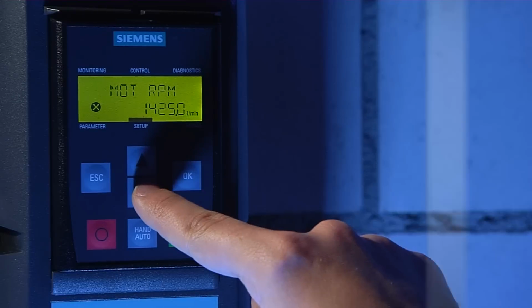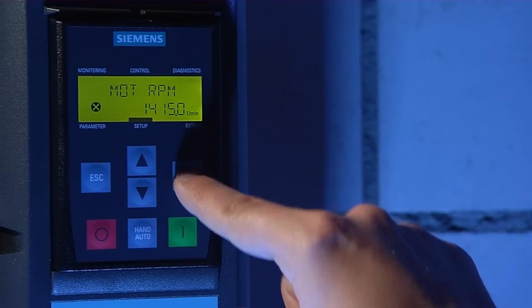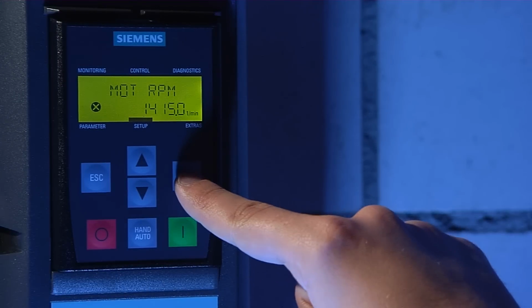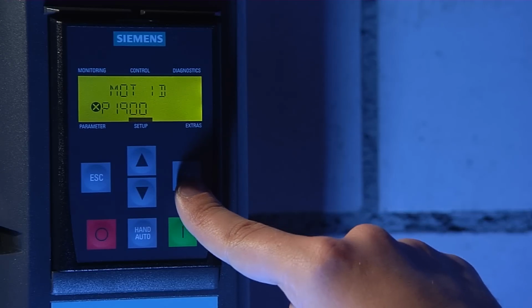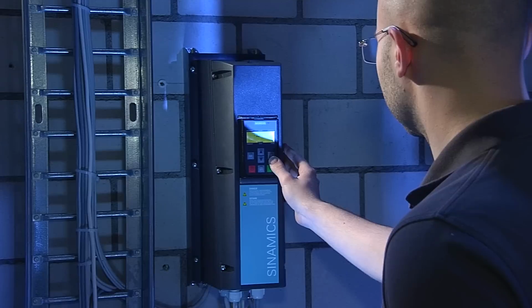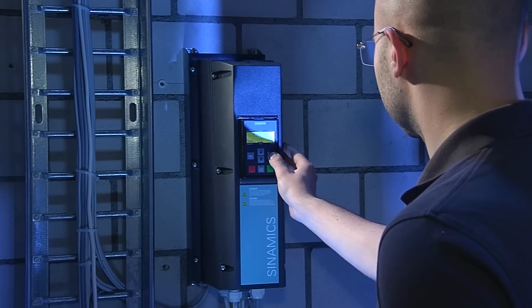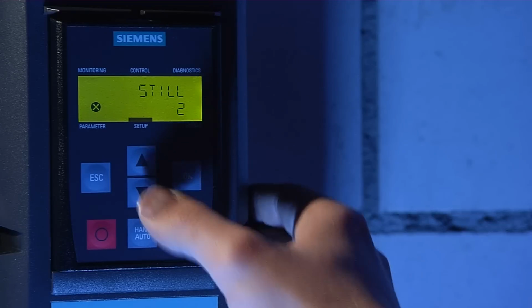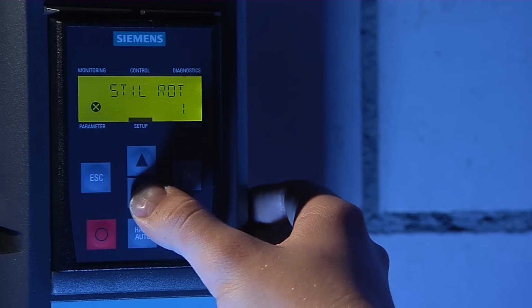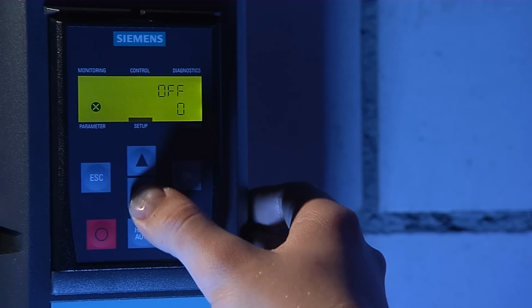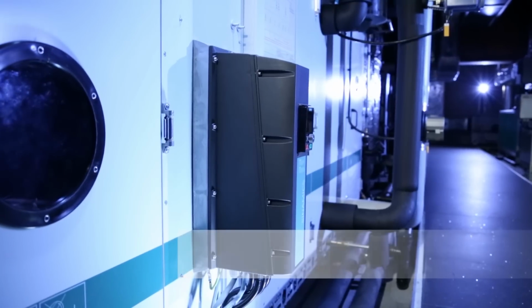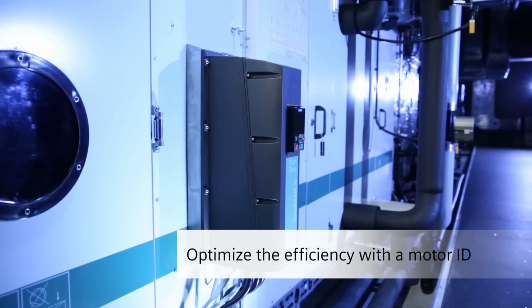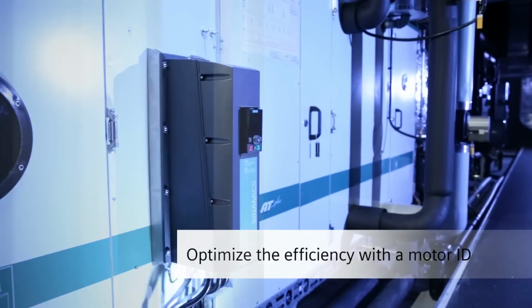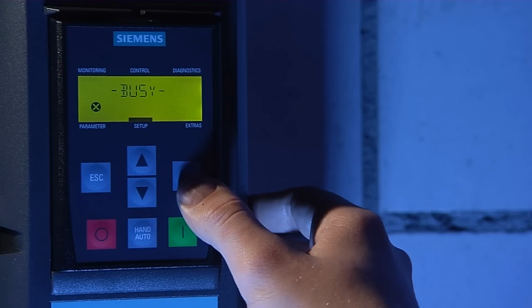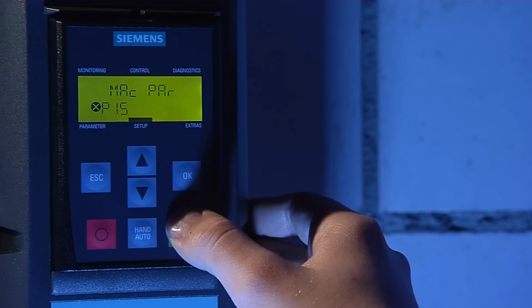In motor RPM, enter the nominal speed of the motor as indicated on the rating plate. It's recommended to always perform a motor ID in order to optimize the settings of your drive. For V/f control, choose Motor ID at standstill. When using sensorless vector control, it's recommended, as long as it's safe to do so, to choose Motor ID at standstill and when rotating. The next step in the setup process is macro parameter P15.